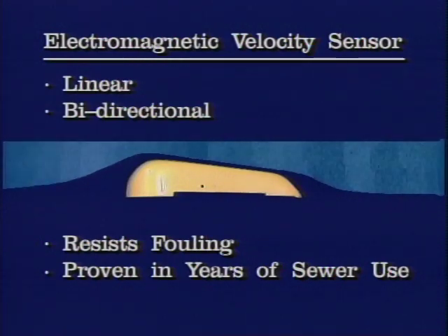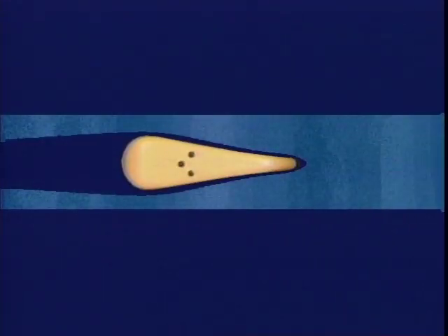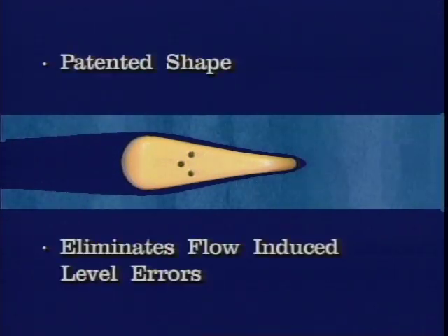Marsh McBirney engineers chose the electromagnetic technique for the probe's velocity sensor because of its proven ability to operate equally well in both raw sewage and stormwater. The electromagnetic technique also allows for high correlation accuracy between sensed velocity and mean velocity. The probe's level sensor operates even in rapid flow environments. The patented shape of the probe virtually eliminates level errors caused by the pitot effect of rapidly moving water. The probe's upswept shape prevents paper and other debris from hanging up on it, so measurements are possible for long periods without fouling.